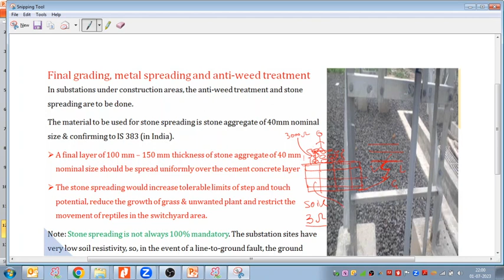The stone is spread for safety. But if your soil resistivity is very low, say 3 ohm, 5 ohm, 10 ohm, what will happen? Whatever fault current is coming will not try to reach the element or equipment placed above the ground, because the soil resistivity is always very low. So it will always flow underground. It will not intend to reach above ground, because the soil offers much less resistance, and we know current flows towards the less resistive path, and the soil is providing the less resistive path. So why should I put the stone above ground?